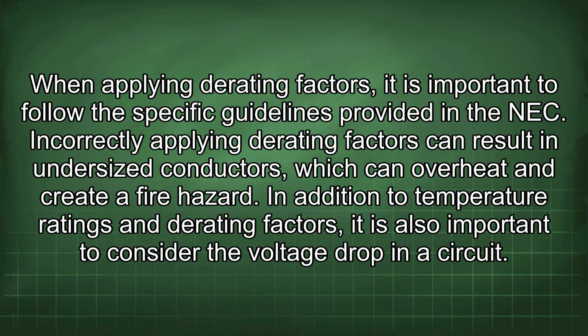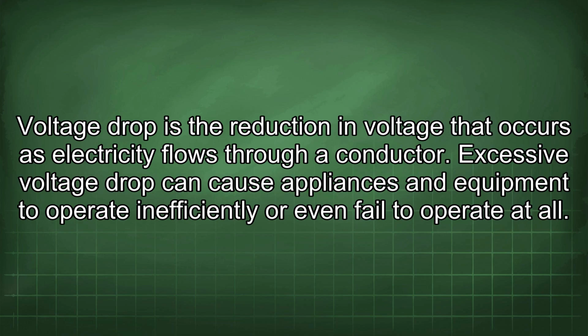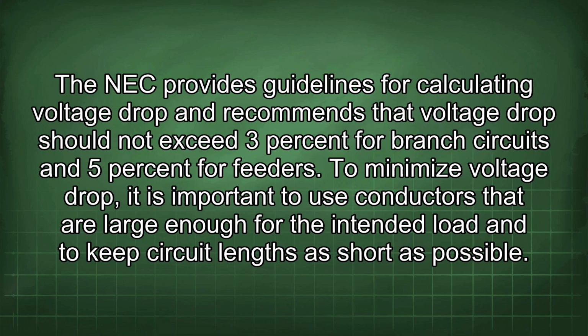In addition to temperature ratings and derating factors, it is also important to consider the voltage drop in a circuit. Voltage drop is the reduction in voltage that occurs as electricity flows through a conductor. Excessive voltage drop can cause appliances and equipment to operate inefficiently or even fail to operate at all. The NEC provides guidelines for calculating voltage drop and recommends that voltage drop should not exceed 3% for branch circuits and 5% for feeders. To minimize voltage drop, it is important to use conductors that are large enough for the intended load and to keep circuit lengths as short as possible.